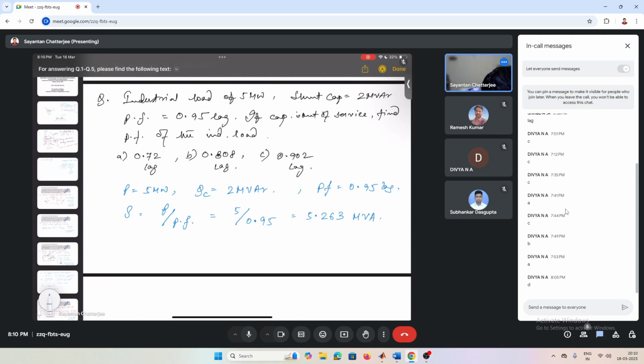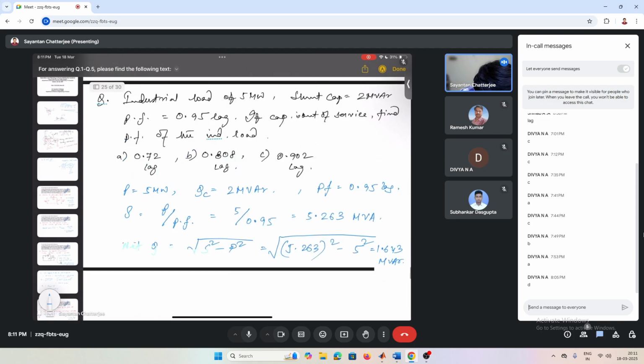Now the reactive power we have used, so net Q will be root of S square minus P square. So this is 5.263 whole square minus 5 square. Taking root, we get 1.643 MVAR, this is Q old. But what we have seen is that there is a shunt capacitor of 2 MVAR connected.